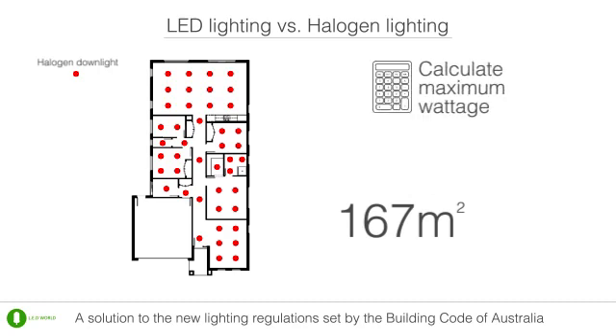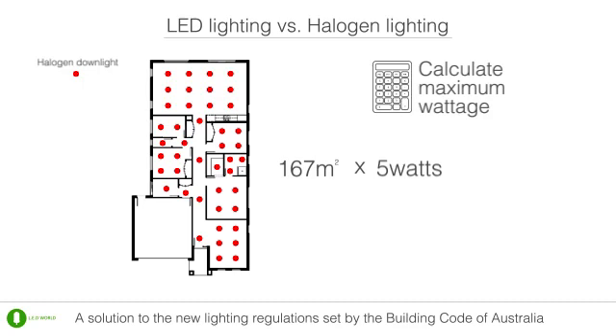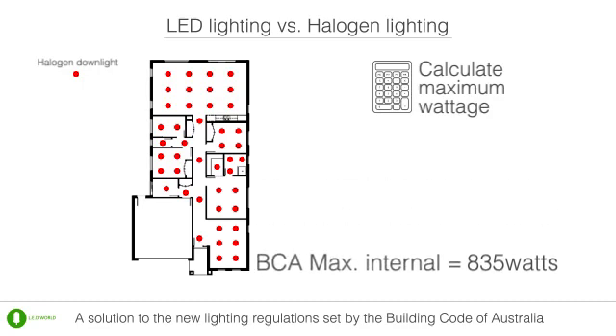Calculating the maximum acceptable wattage a house can have to comply with the new BCA regulations is easy. Simply take the area of the house in square metres and multiply it by 5 watts — 5 watts per square metre is the new energy limit. The example house plan pictured here has a maximum of 835 watts for the entire internal area. Now, multiply the total number of downlights in the house by 50 watts, as the standard halogen downlight uses 50 watts of energy. The example house is using 44 halogen downlights, therefore it has an internal usage of 2,200 watts.